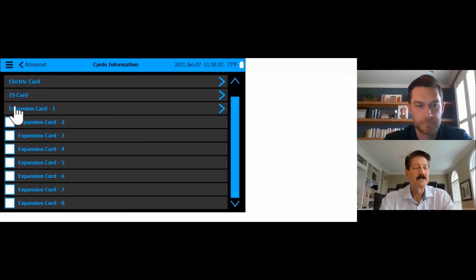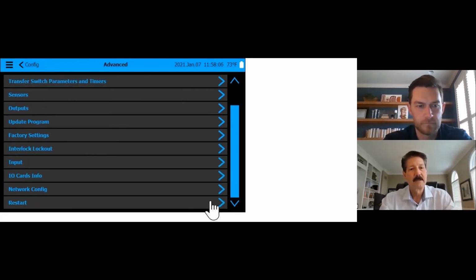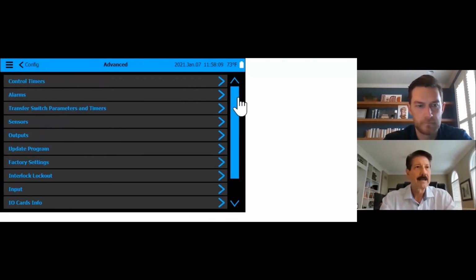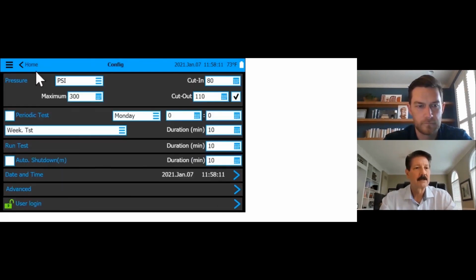Pretty easy stuff, but we'll normally send an update if it's done in the field. It's a good point. So again, our remote alarm contacts are 2 open and 2 closed. So that's quite nice, because especially with diesel, if you're running an engine run and you have maybe an alarm or a light, a strobe, you can do that too.